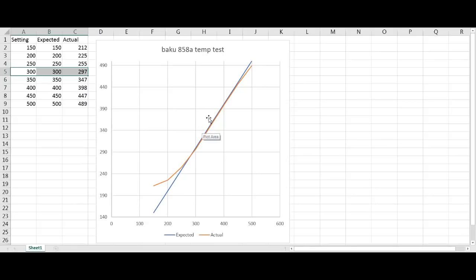So even though there's a calibration pot in the unit, it only sets a single point and doesn't adjust the curve of the line. It looks kind of exponential here and maybe a little bit exponential here, almost like an S-curve. That's a good indication that whoever did the control theory and control loop on this device didn't do a really great job. You see that a lot with Chinese test measurement equipment, lots of times when control loops aren't done very well, and here we see it again.